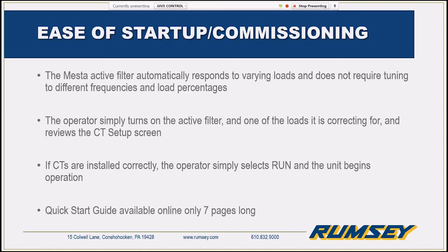Older active filters needed to be loaded and tuned to certain loads, and that's oftentimes with many different types of passive filters being tuned to certain frequencies. So when the active filter is turned on and there's a little bit of load on, they just go to that CT setup screen. If the CT setup screen says they're good to go, they just hit run. So nice and easy. Quick Start's 7 pages long, and the first few pages are warnings so that you don't shock yourself. So real easy to use.